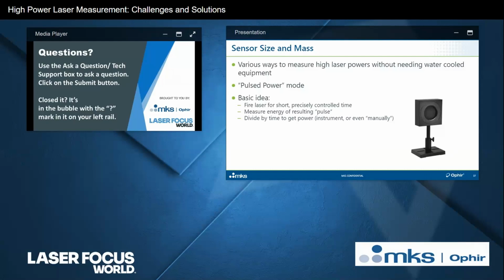Okay, obviously that's a bit trivial, but we can do this semi-automatically, whereby we know the pulse duration, the pulse width as we call it, and we can have a meter that prompts us to enter that known exposure time. It will measure the energy. It'll ask us to input the time, and it'll do the math for us. I'm going to refer to that as semi-automatic. We have a bunch actually of Ophir meters that have that function, that mode built in.